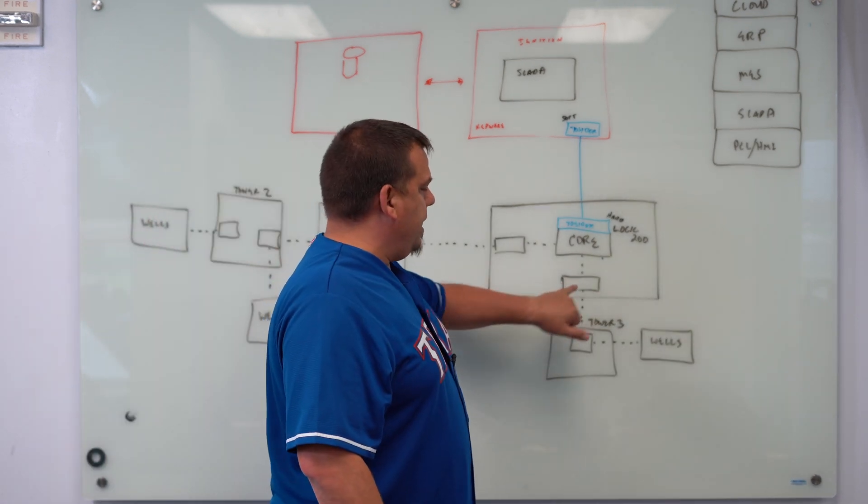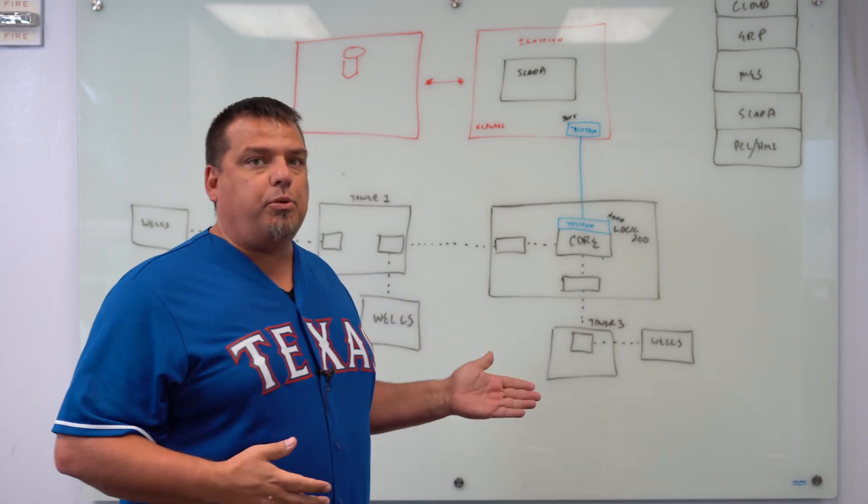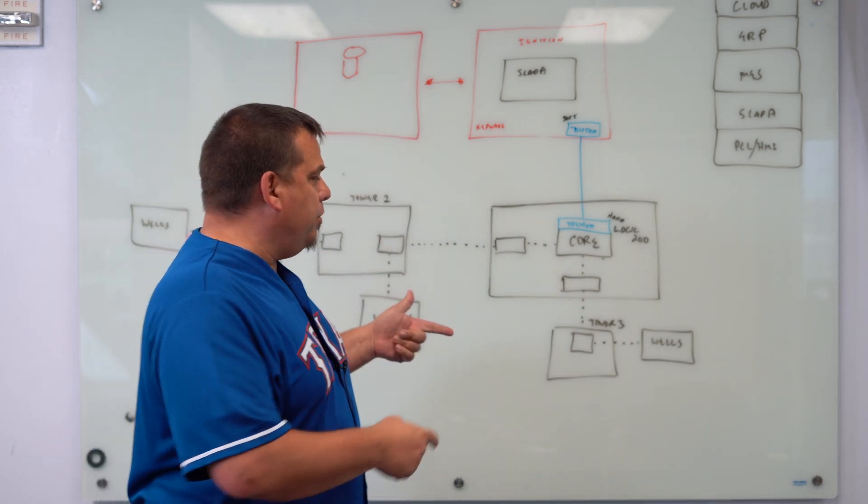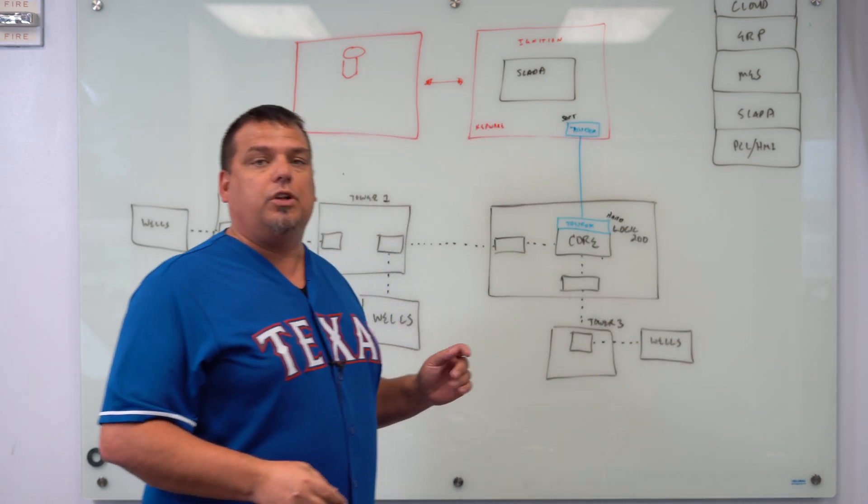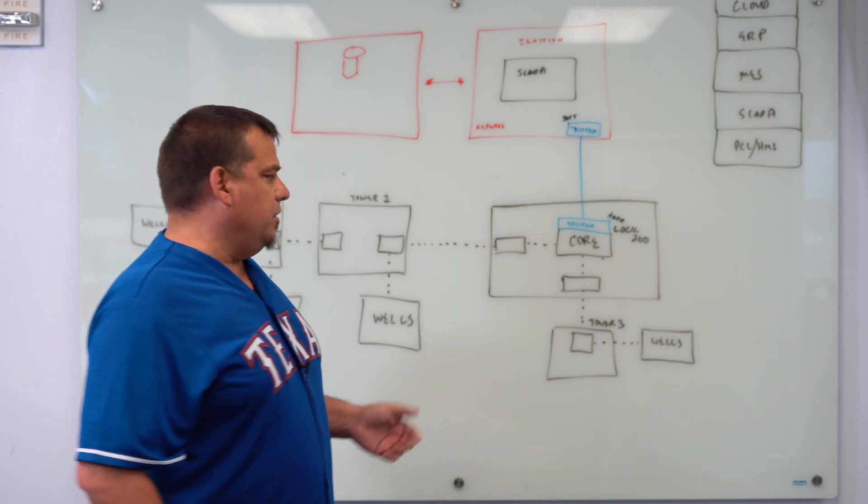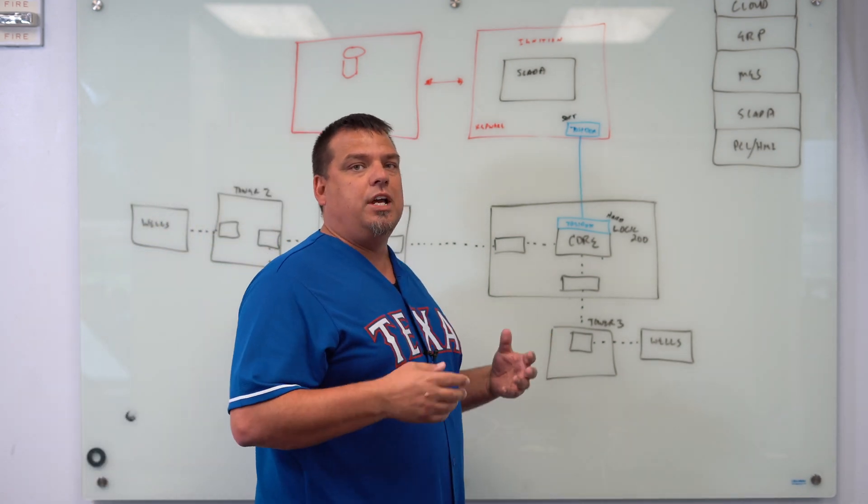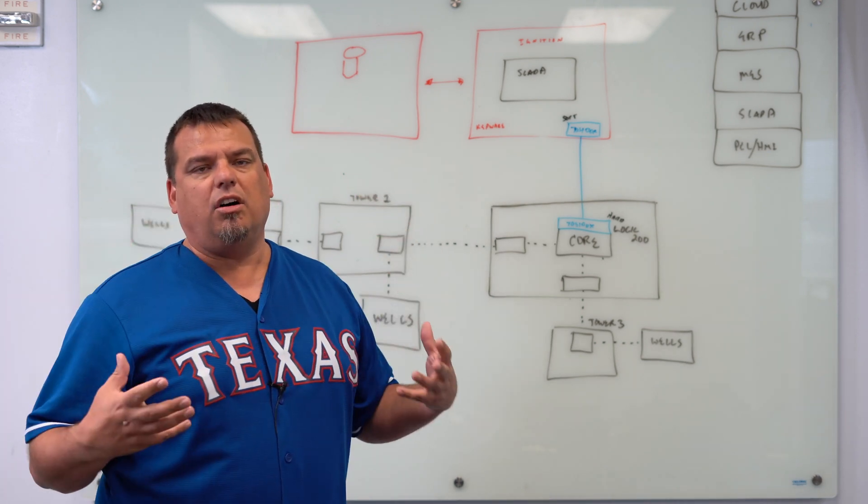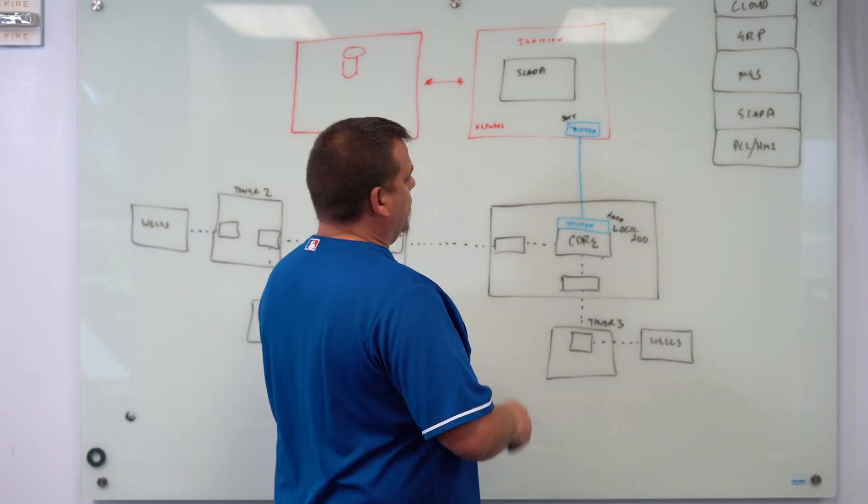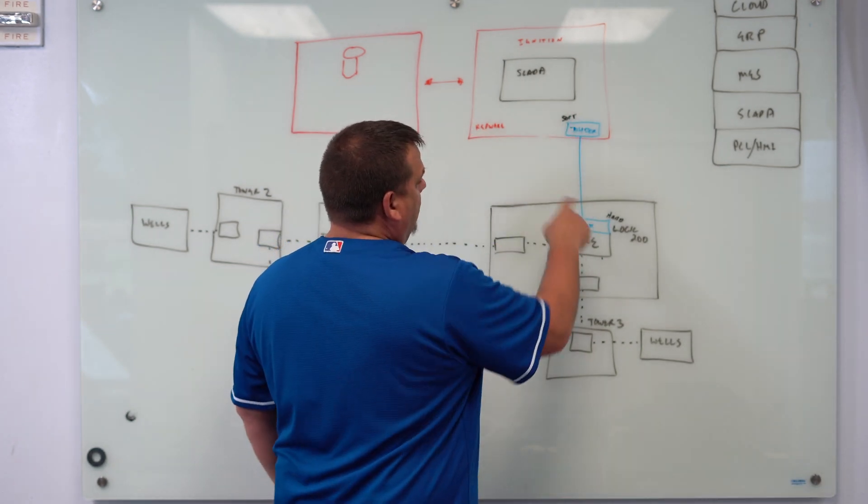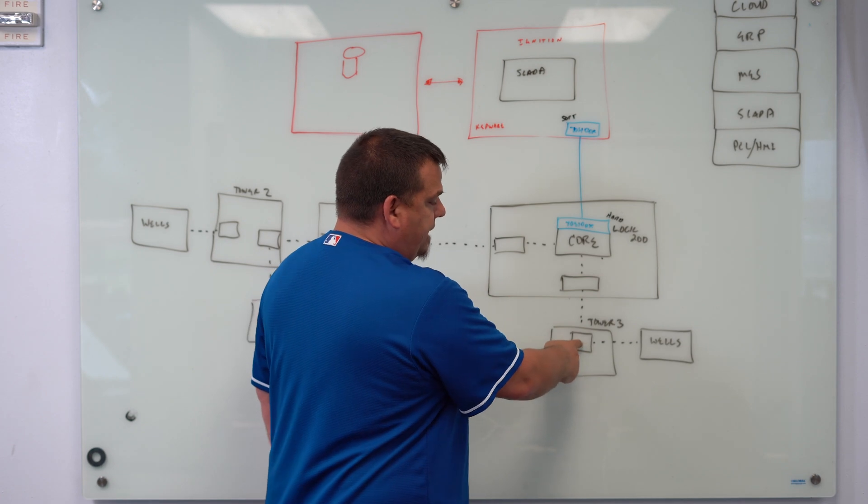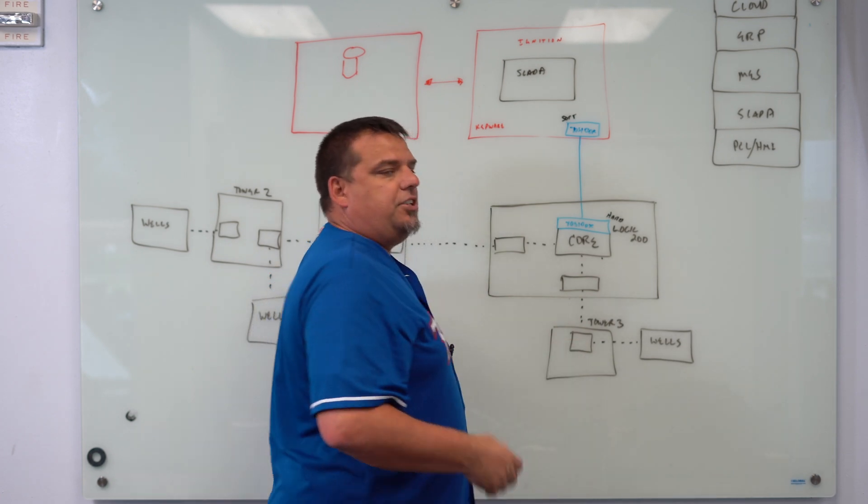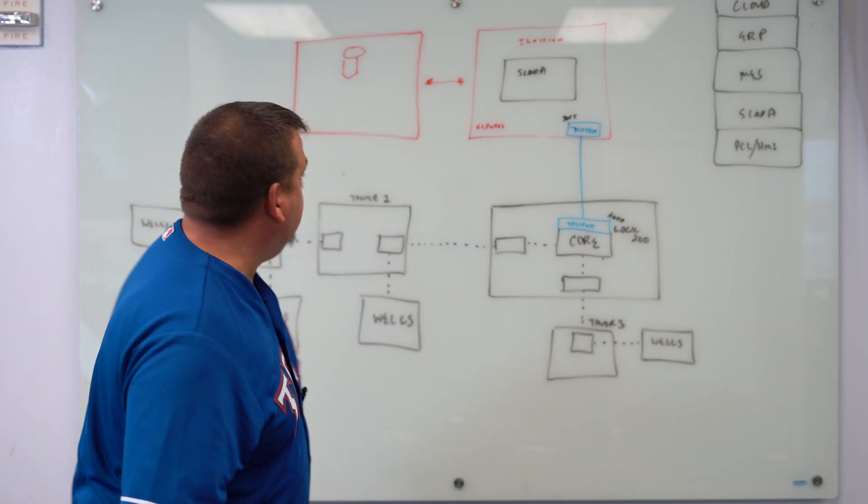This radio talks to that radio. There's a master radio that has a serial port on it, and that serial port is essentially daisy-chained to all of the ABB total flows that are controlling the oil wells in the field. The way that you talk to these ABB total flows, which is where we're going to get all of our tubing and casing pressure and all of the process data that we care about from these wells, is we're going to use Kepware.